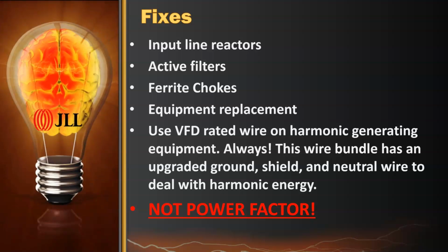So ferrite chokes are basically a round iron core, a round piece of iron. It's hinged and allows you to open it up and clamp it around the conductor. Same thing as the input line reactor, it acts on the magnetic field in the conductor, and it reduces the amplitude of that magnetic field. Of course, when it does that, it cuts into the energy generated by the harmonic that's creating that bigger magnetic field. So the ferrite choke will warm up a little bit. It might get up to 100 degrees or 105. It won't go to 110. It'll just be a little warmer.